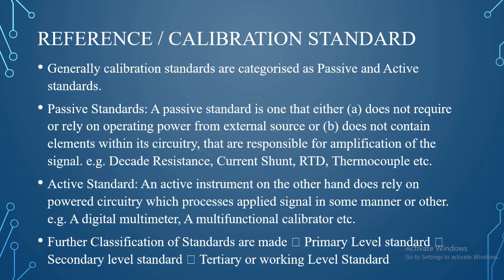Now, what is meant by reference or calibration standard? Generally, calibration standards are categorized as passive or active standards. Now, which are the passive standards? A passive standard is one that does not require or rely on operating power from an external source. And second, it does not contain elements within its circuitry that are responsible for amplification of the signal. For example, decade resistance, current shunt, RTD, thermocouple, etc.